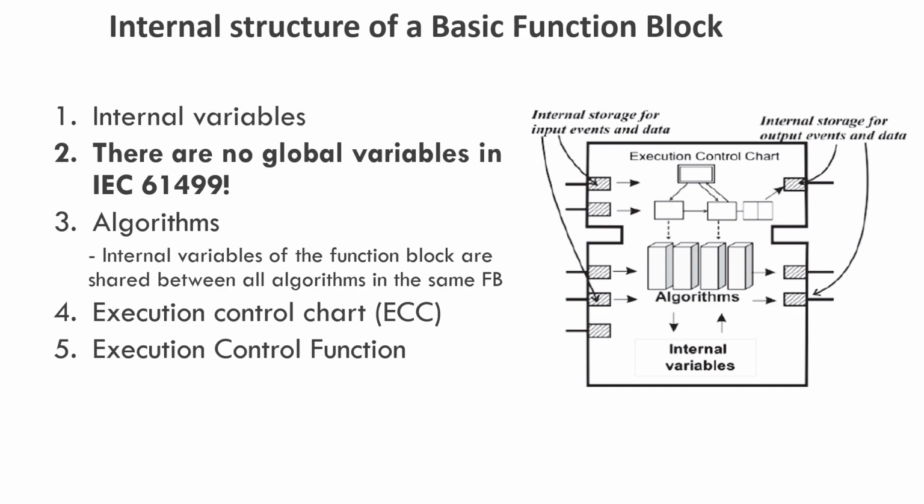And there is an execution control chart that is a state machine describing how the function block reacts on arrival of input events and how it calls algorithms and what happens after algorithm is executed. So all these algorithms are connected with each other using execution control chart.